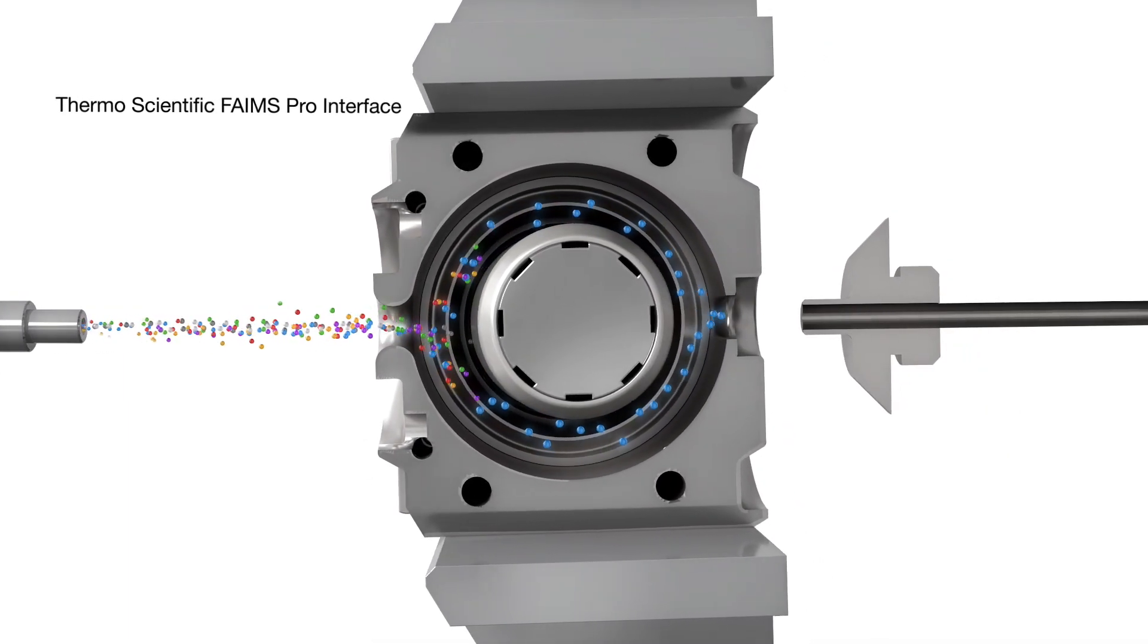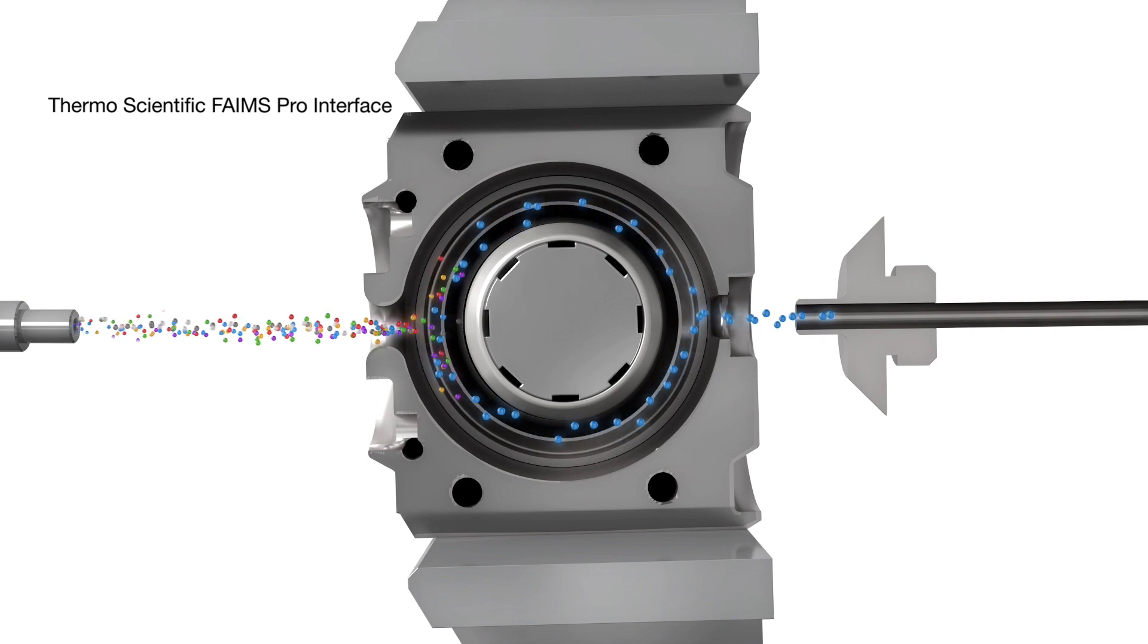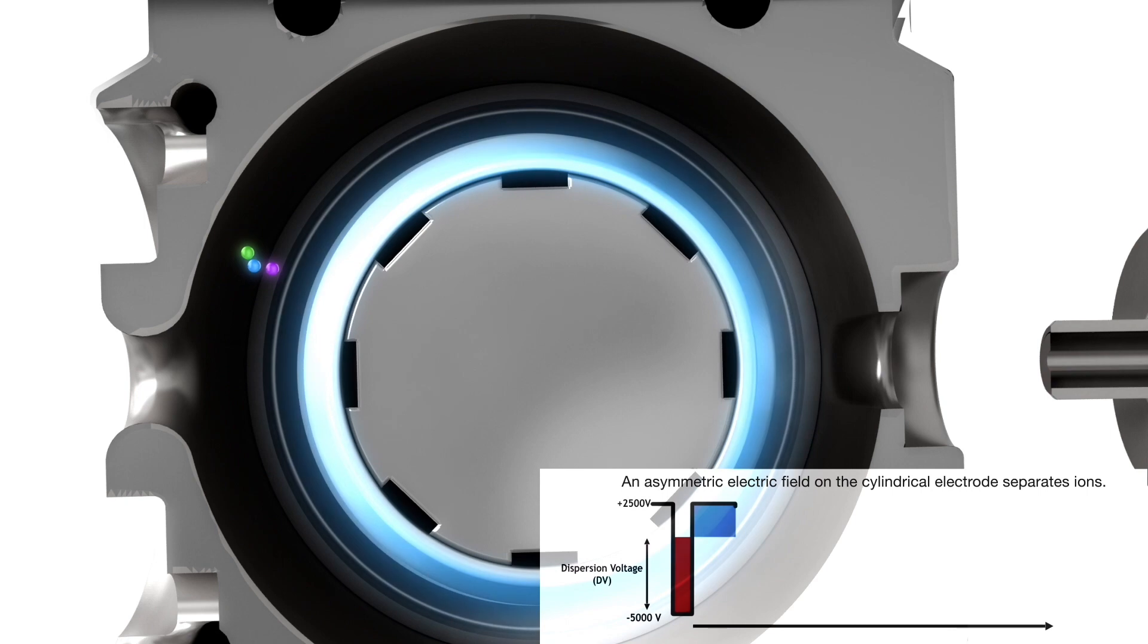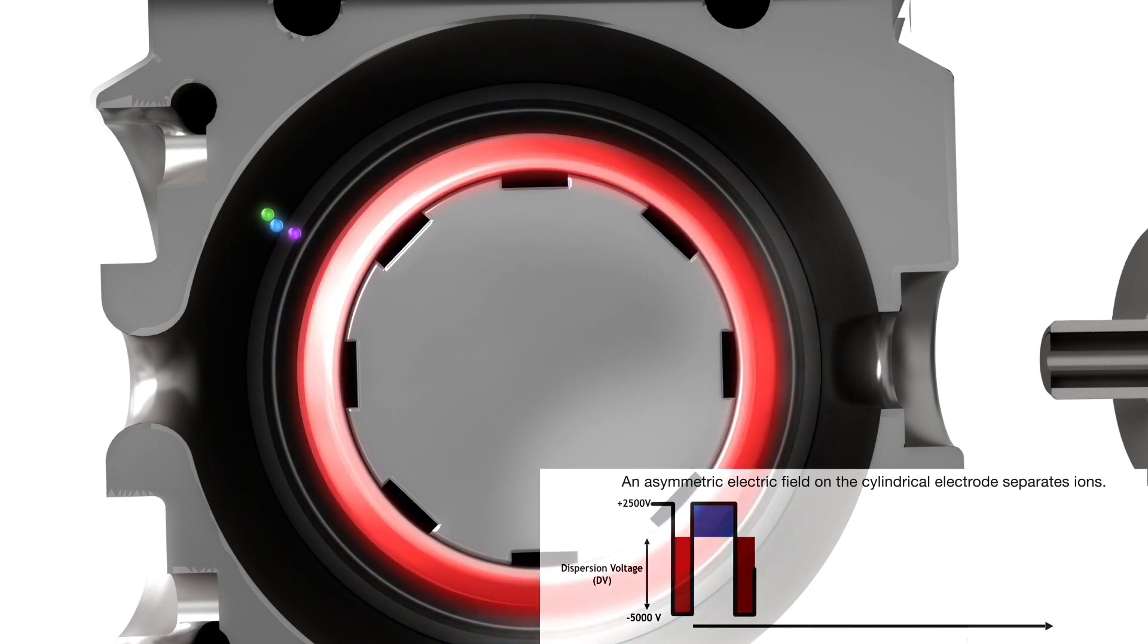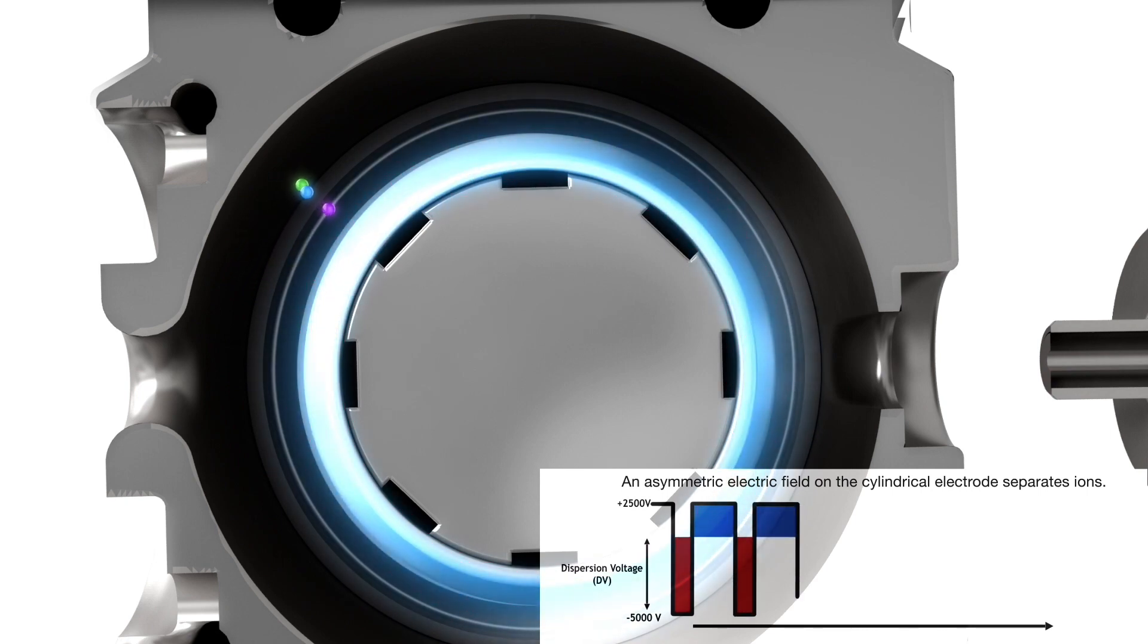The FAIMS Pro interface is placed between the electrospray emitter and the mass spectrometer entrance. An asymmetric electric field, the dispersion voltage, is applied to the inner cylindrical electrode to separate ions as they traverse the interface in a flow of nitrogen.